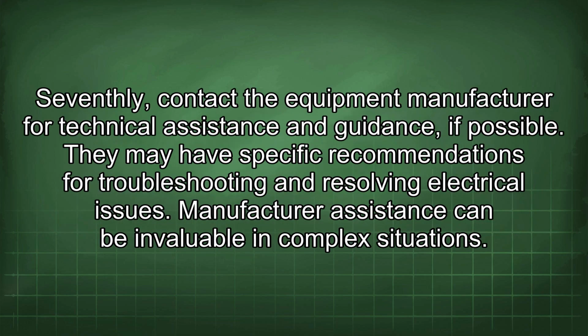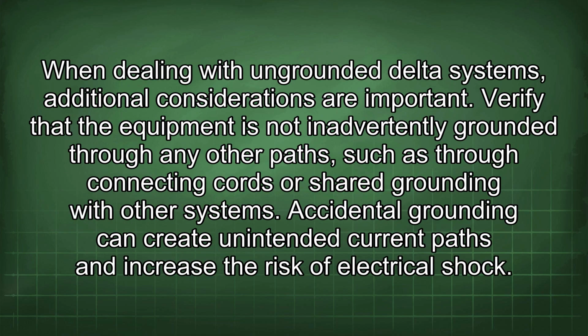Seventhly, contact the equipment manufacturer for technical assistance and guidance, if possible. They may have specific recommendations for troubleshooting and resolving electrical issues. Manufacturer assistance can be invaluable in complex situations. When dealing with ungrounded delta systems, additional considerations are important. Verify that the equipment is not inadvertently grounded through any other paths, such as through connecting cords or shared grounding with other systems. Accidental grounding can create unintended current paths and increase the risk of electrical shock.